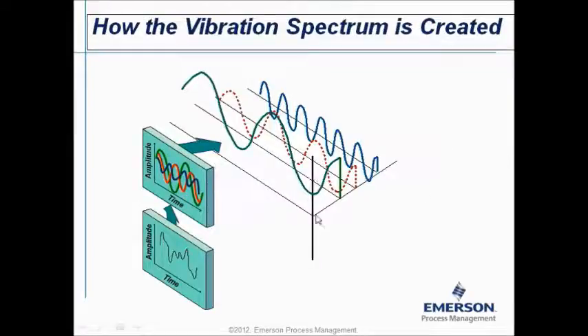Now, what is this information telling us? Remember, an imbalance was 1 sinus per revolution. That is relatively slow speed, so that will be on the left side of this axis. So this peak here is your energy coming from your imbalance. Now the bearing problem creates several impacts per revolution, so it goes faster, the energy is created faster, so it's more to the right side. Now I simplify a lot of things, so don't take this as a complete and correct vibration theory. Once again, I simplify a lot of things, but this is the energy coming from your imbalance, and this is the energy coming from your bearing problem, for example.